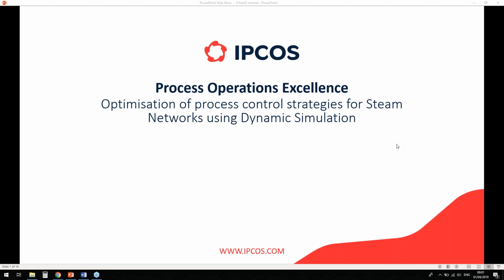This presentation on steam networks control will cover the details of a steam network whose process control philosophies were optimized using a rigorous dynamic model. The objective of the study was to understand the impact of changes in the topology of the steam network, and also analyze the dynamic impact on the steam network of choosing different control philosophies. The study resulted in several benefits, such as improved understanding of the steam network and dynamic interactions, and how better to operate the system to improve steam network pressure control.